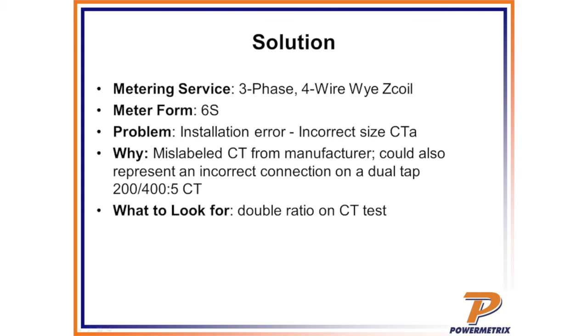You just may look up and see, well, I got a pass, but why the heck is it a 400:5 ratio? So hopefully you should use your eyeballs and try to figure that problem out if that happens. But in this case, the technician actually selected a CT in the database and then ran it. And then the PowerMaster saw that this doesn't match what's in the database, so this has got to be wrong. So good info.